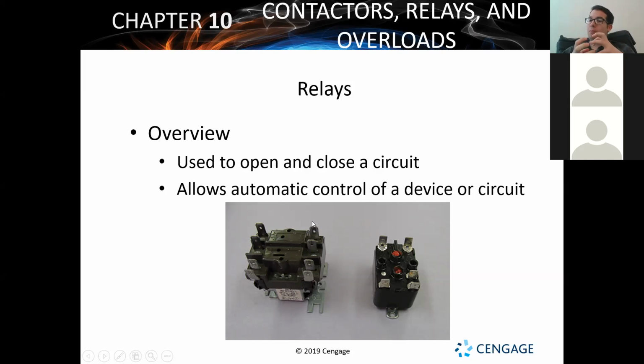It's contained in plastic or thermoplastic casing - I've seen it clear, brown, black, all sorts of different colors. Because of that, we're not going to be able to visually inspect these much for that mechanical linkage. We're going to have to actually test: what's the voltage coming in, what's the voltage coming out, what's the voltage across from one terminal to the other, and are we having power pass through or not?